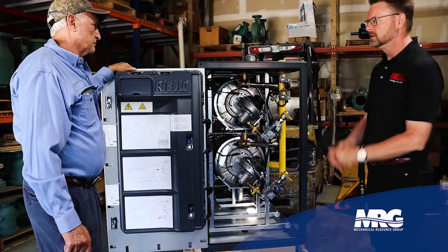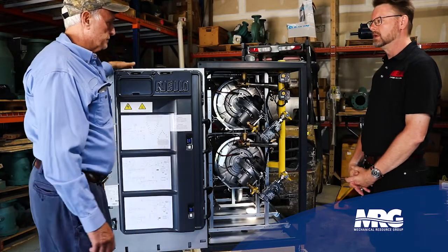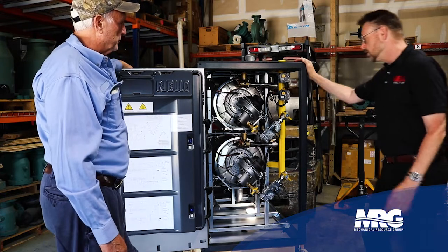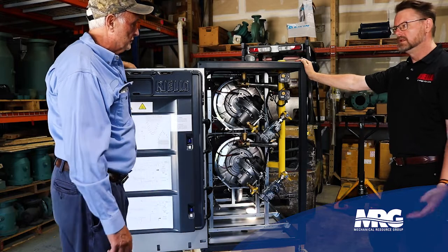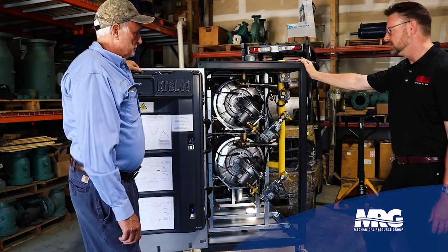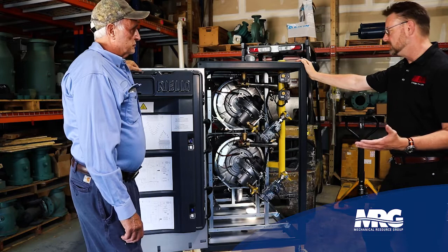How much capacity do you lose when you lose the flame safeguard on a conventional boiler? Everything. You lose the whole thing. It doesn't matter if it's 20 to 1 or 10 to 1 or 15 to 1, because you have no redundancy. The loss of a flame safeguard is the loss of the unit.